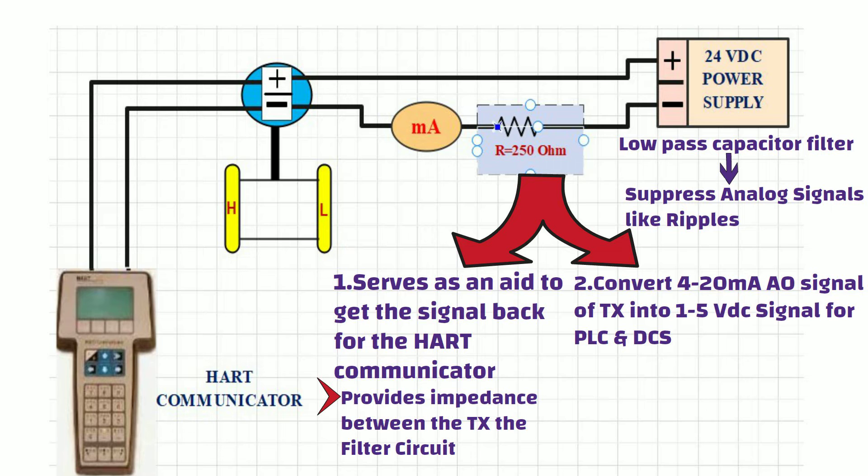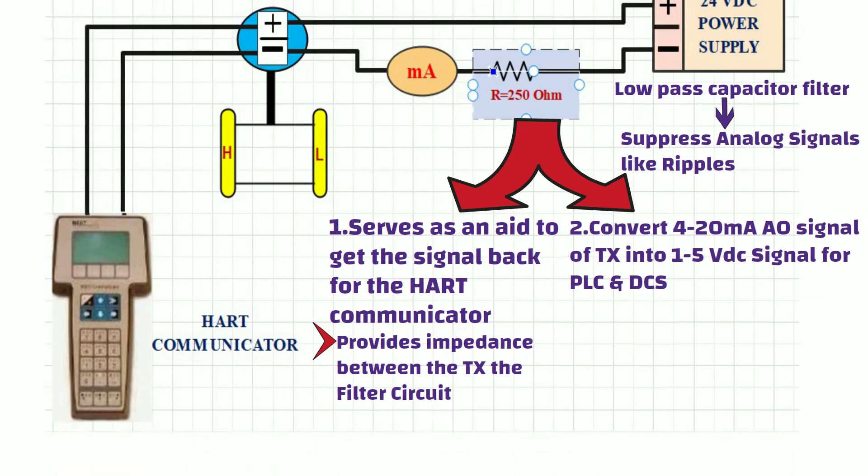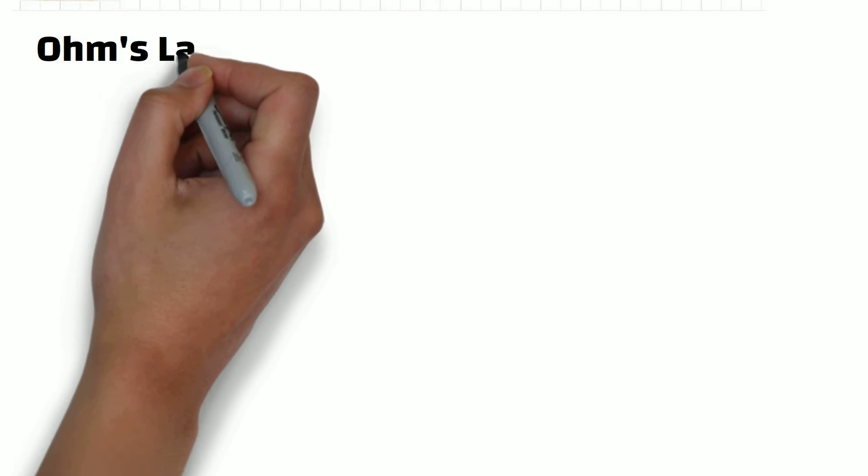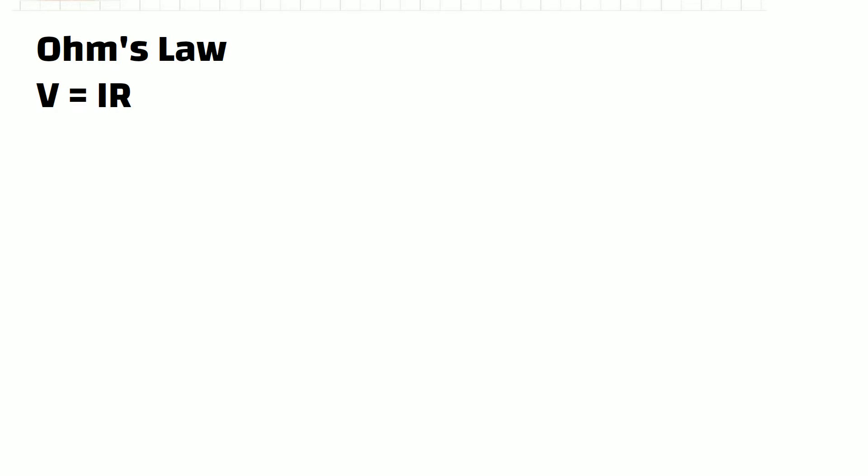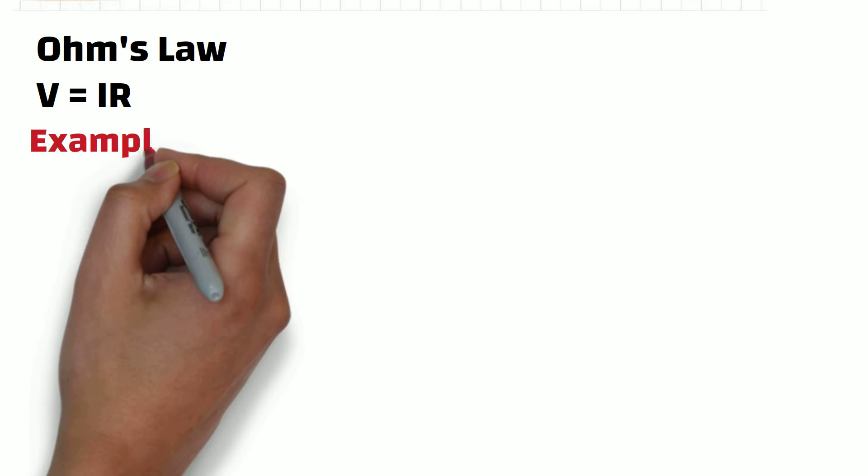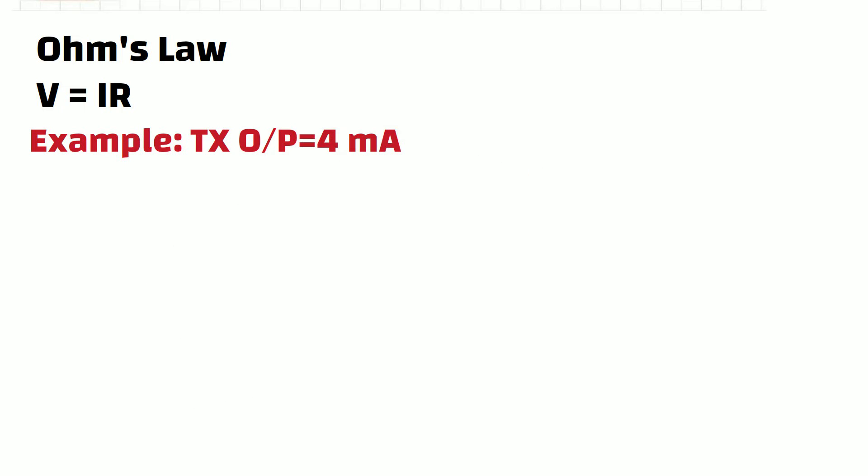Let me explain you this thing by taking Ohm's law examples. As you can see, this is the equation of Ohm's law. Let's assume that transmitter's output is 4 mA, and we have 250 ohm resistor in the circuit. Now, put all these values into equation, and do the simple math calculation. You will get 1 volt DC as a result.